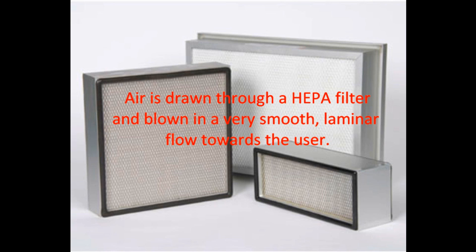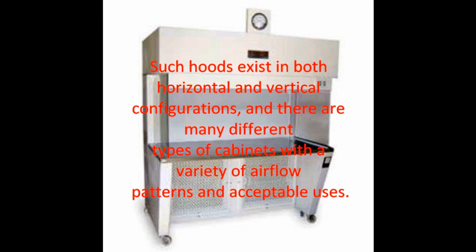Air is drawn through a HEPA filter and blown in a very smooth laminar flow towards the user. Such hoods exist in both horizontal and vertical configurations, and there are many different types of cabinets with a variety of airflow patterns and acceptable uses.